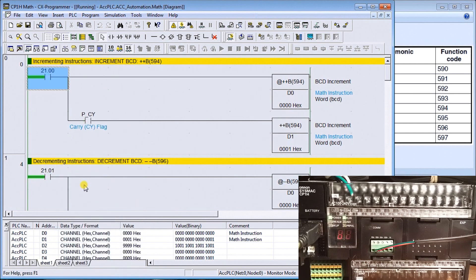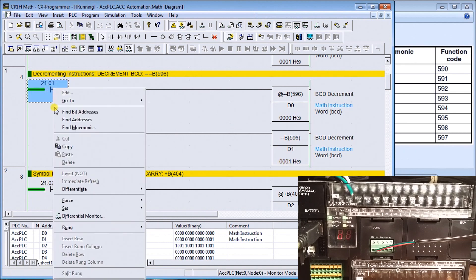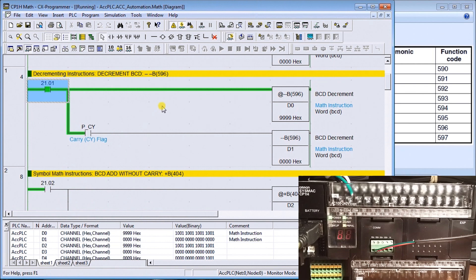We'll set that off and go to the next one, which is decrement. Decrement is basically the same thing. Once we get under zero it goes to 9999 and sets the carry flag, which then decrements data memory one, which now contains the value one. We'll set that on and that's exactly what happens — data memory zero becomes 9999. So we've created addition and subtraction within the Omron PLC using two words, data memory one and zero, and we could expand that to have quite a large word.